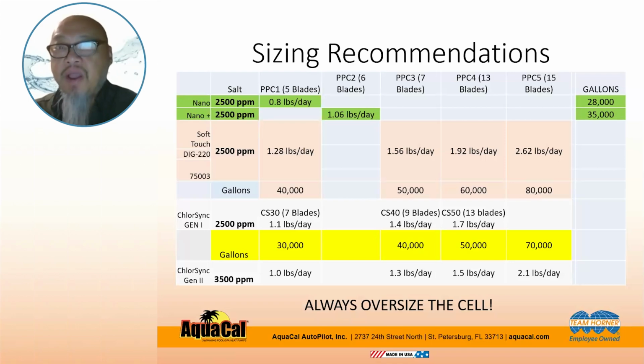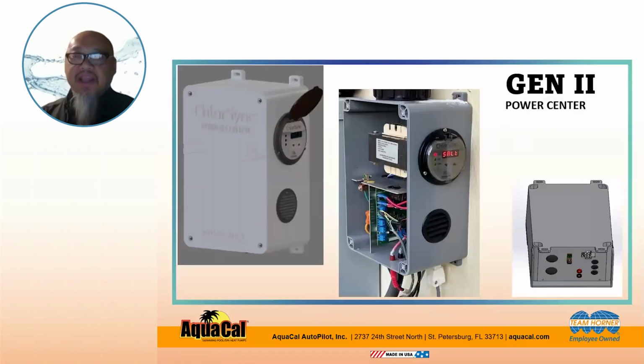hydroxide byproduct. So when you oversize a cell, what that allows you to do is to run it at a lower output, so the cell does not operate as long, which means the pH is not impacted as much. All right. So always oversize the cell. It's always going to be the best recommendation to provide longevity of the cell and to avoid the pH rise and the cell scaling up. All right. So let's take a look at the Gen 2 Power Center.